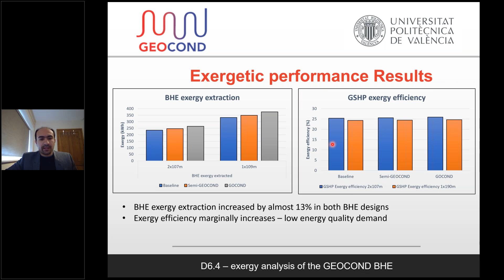Then the exergy efficiency and the BHE exergy extraction are both very sensitive to outdoor air conditions. We can see the green profile here is the outdoor dry bulb temperature, while the red one is the BHE exergy extracted, both averaged over 24 hours so we can see the trend better. Without going into depth, one can notice that as the outside temperature drops, the BHE extraction rate can actually increase.